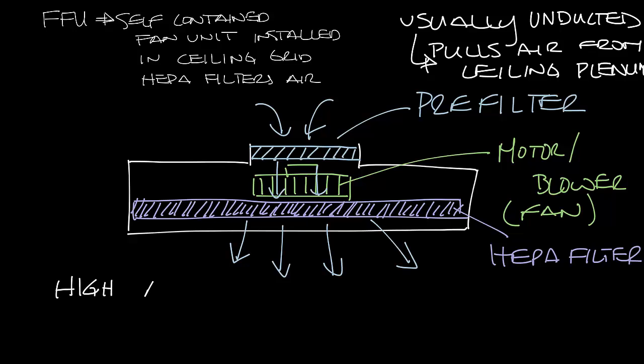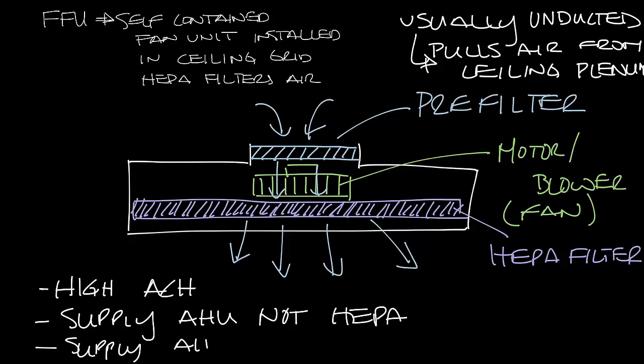You'll often see fan filter units when the room air changes per hour requirement for a space is high, when the supply air handler isn't HEPA filtered but a certain space needs HEPA filtration, or when the supply air handler cannot handle the pressure requirement for HEPA filtration.